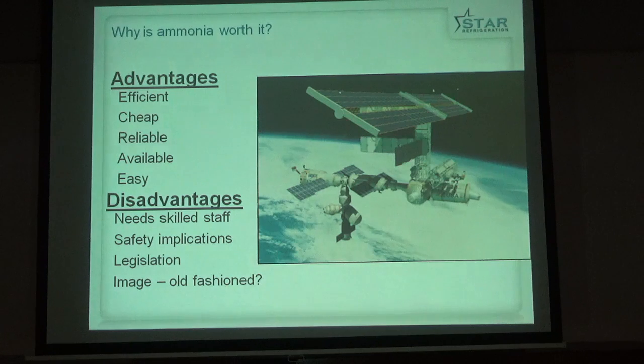This is the International Space Station. NASA looked at 12,000 different possible refrigerants, and they picked ammonia as the refrigerant for the cooling system on the International Space Station. Now, the one thing I don't understand is, in the European standard EN378 on refrigeration safety, it says that the plant room needs to have emergency exit doors that open outwards. And this doesn't seem like a very good idea on the International Space Station. But they didn't do it that way.